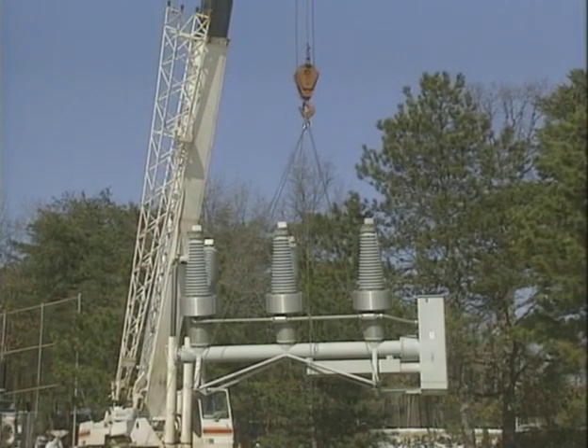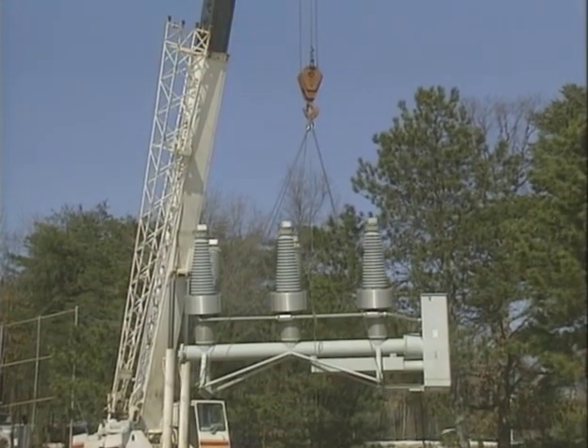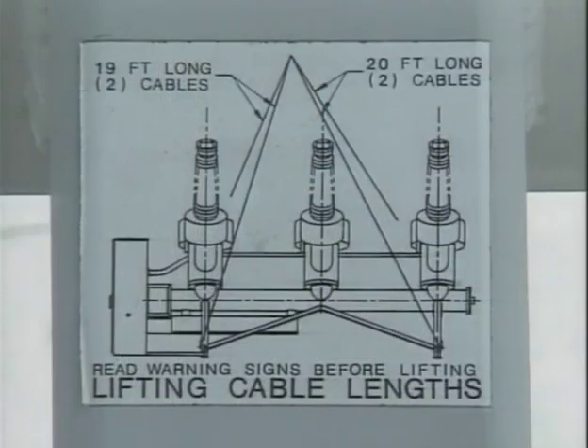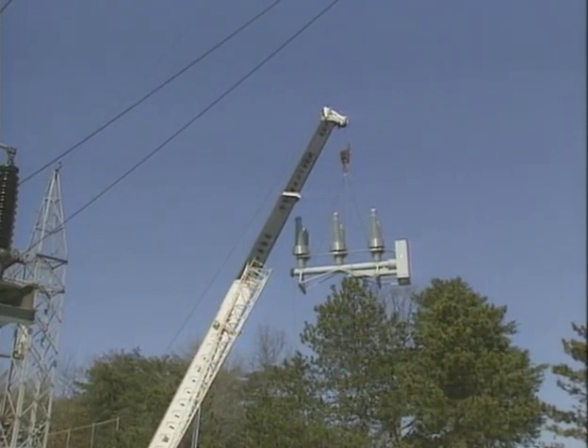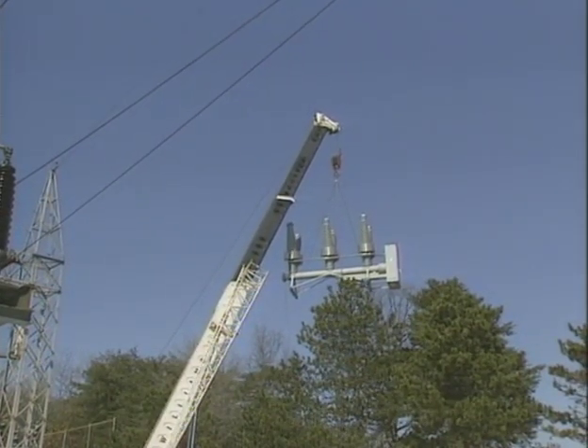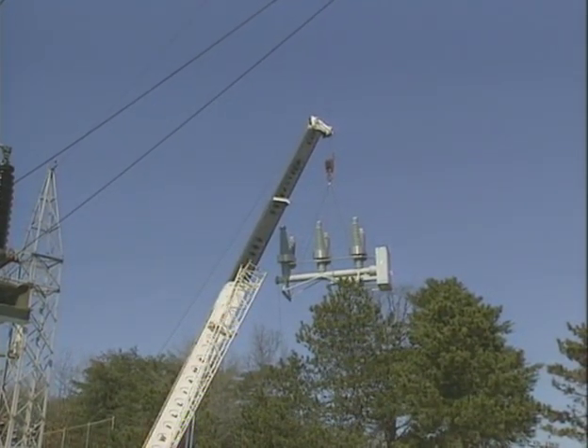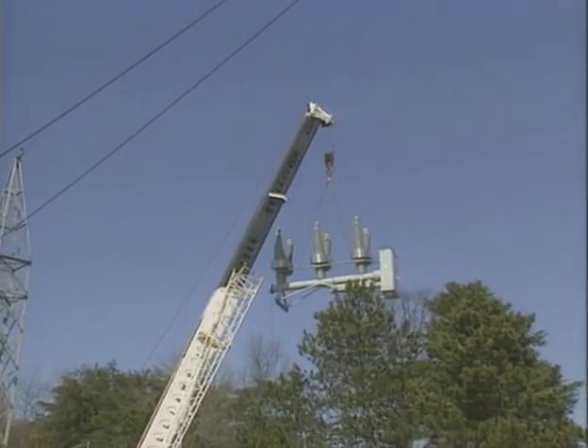The weight of a breaker is often unevenly distributed, so the manufacturer's instructions may specify that the slings to the heavier side of the breaker should be shorter than the slings to the lighter side of the breaker.